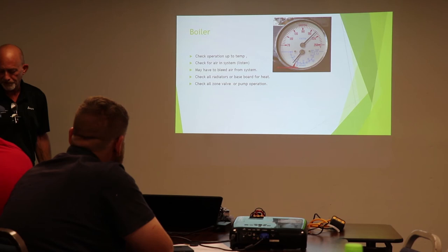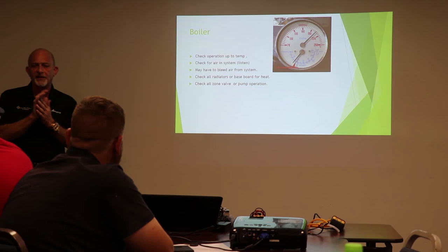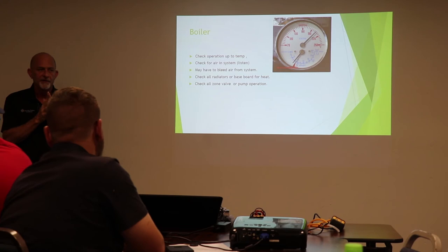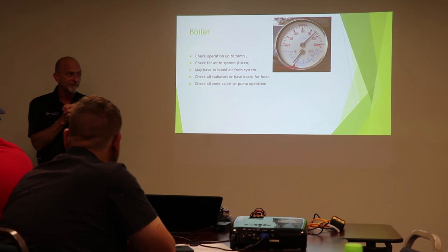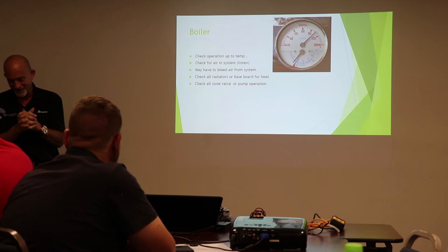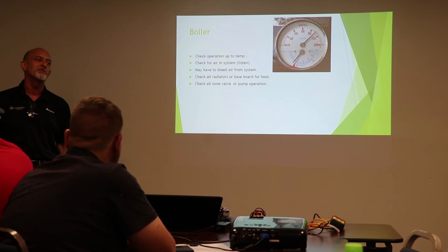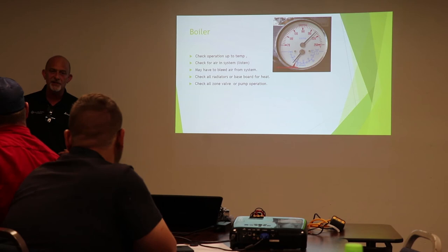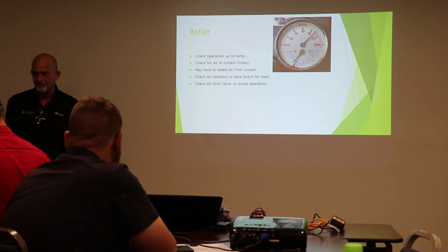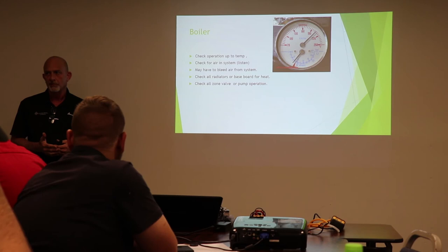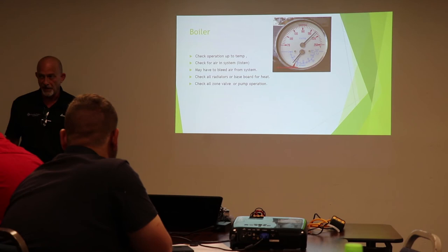One thing, don't ever check to see if a temperature pressure relief works or not on a boiler. If it's not leaking, leave it alone. Because if you open it, most likely it will leak after you touch it. So now you gotta take the boiler down, replace the temperature pressure relief, put a new one in. If the relief opens, there's a reason. Most likely the tank's bad, we're building too much pressure up. Or somebody tried to adjust a pressure reducing valve for your inlet water and turn it up past 12 PSI. Because they are factory set at 12.